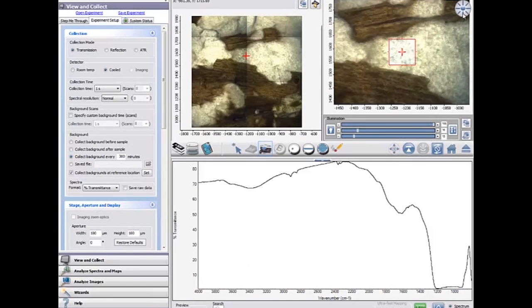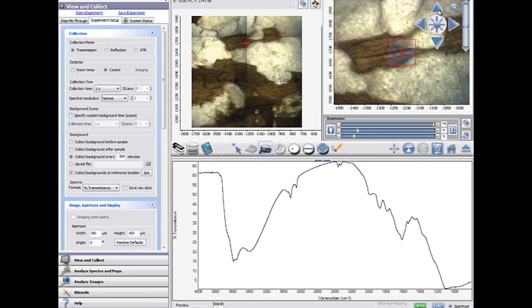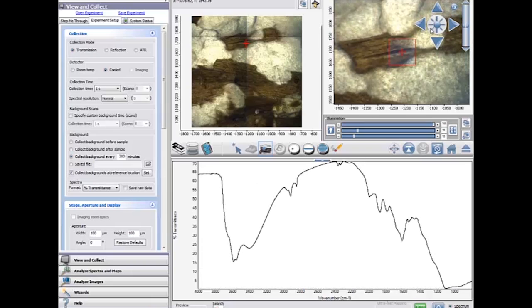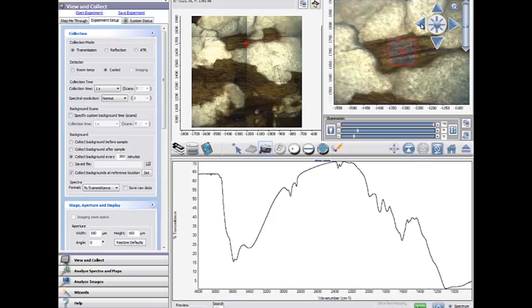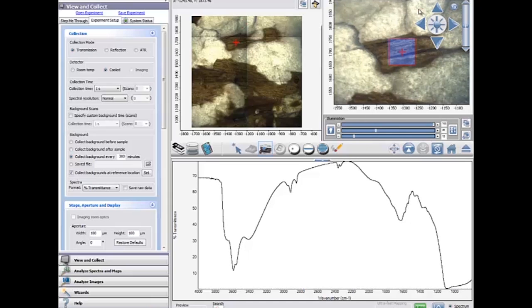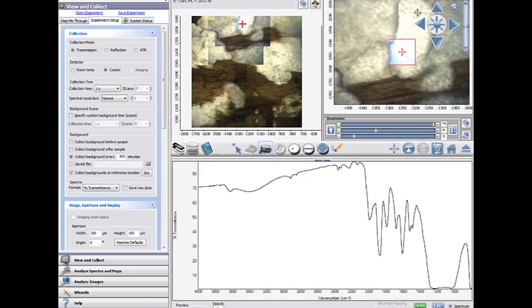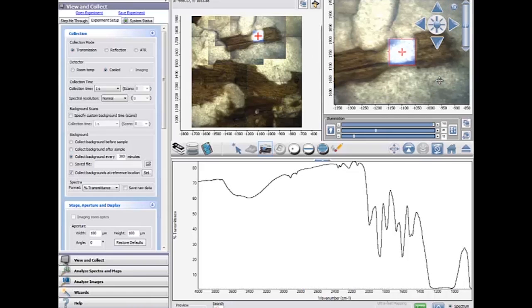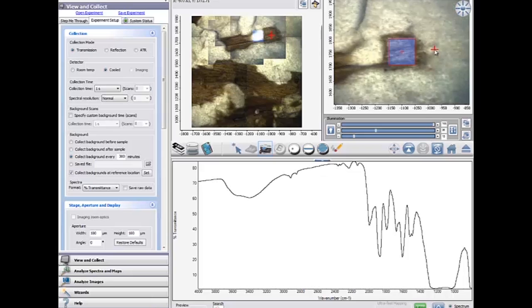You graphically select the specific point for analysis using the automated aperture system. The off-axis aperture never blocks your view of the specimen. A backlit illuminator physically confirms you have selected the correct region of interest. These active preview scans are a result of a single scan.